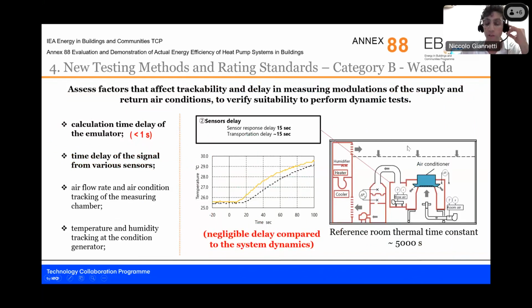As a first part of this activity, we focused on making sure that the measuring procedure is reliable and reproducible across different facilities. So besides accuracy of the sensor, we had to look into all the sources of thermal and transport delay that occur inside the testing facility, and we addressed them by observing if they're negligible compared to the time constant of the operation of the system, like in the case of the calculation time of the room emulator or the delay coming from the sensors themselves.